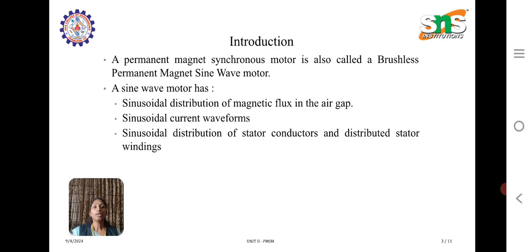A permanent magnet synchronous motor is also called a brushless permanent magnet sine wave motor since it is an AC input motor. A sine wave motor has a sinusoidal distribution of magnetic flux in the air gap, sinusoidal current waveforms, and sinusoidal distribution of stator conductors with distributed stator windings.